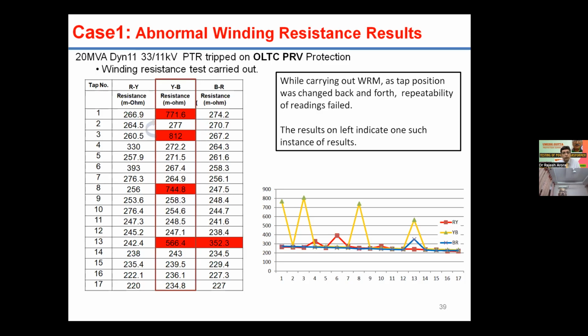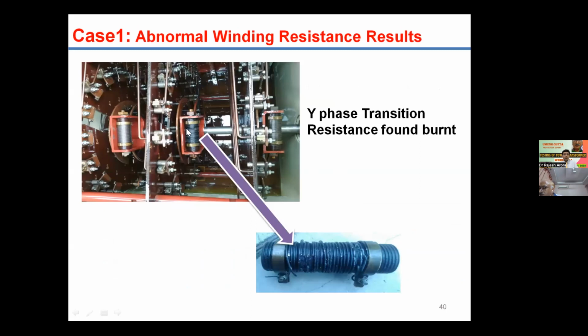So what we did was we tried to move back and forth on different taps, from tap number 3 to 2, and then coming again back from 2 to 3. Every time we noticed that when we are changing the tap, the resistance value is different. So basically the repeatability of resistance values failed. Thereafter, we took another winding resistance kit also, and we tried to test with that kit. Again, the same pattern was there. So we were sure that there is some kind of fault definitely there in the transformer. So we went for the inspection of the transformer through the inspection window. What we found, as you can see in this picture, was that the Y-phase transition resistance was found to be burned. And ideally speaking, this transition resistance comes into the picture only when we are changing the tap.